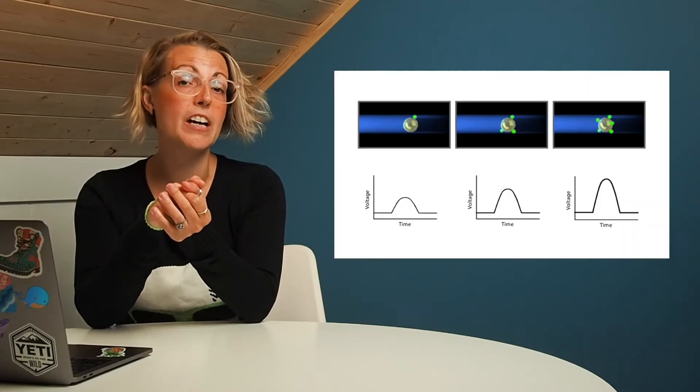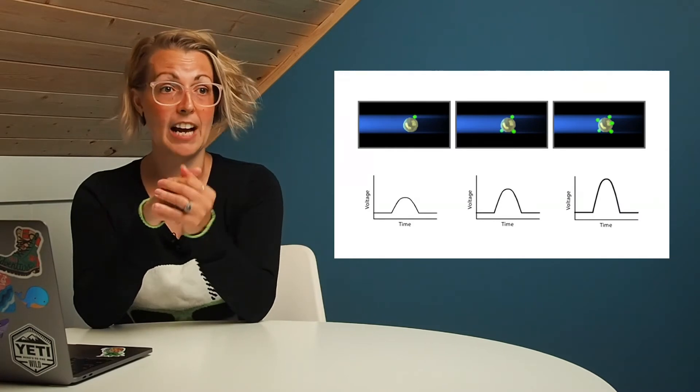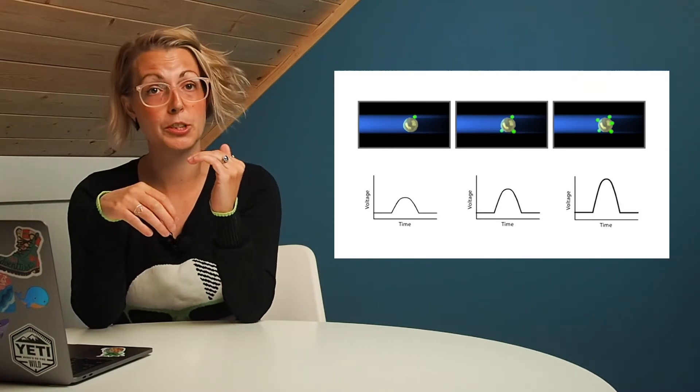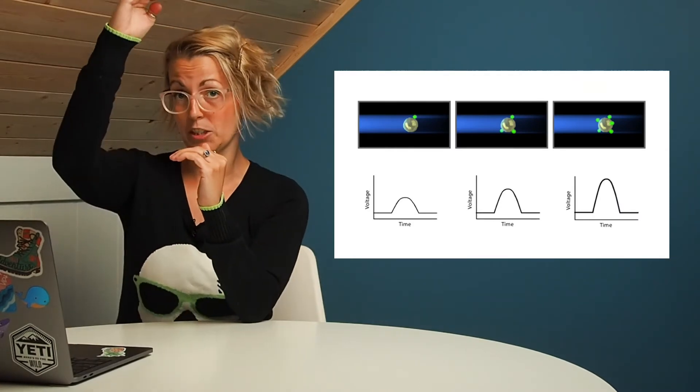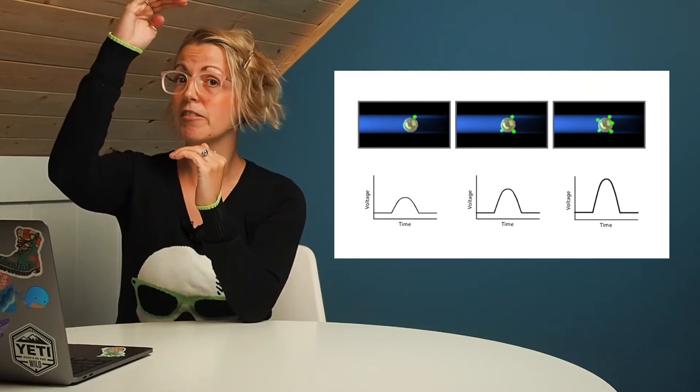When you look at your fluorescence data, you'll notice that some cells have a low level of fluorescence, and some cells might have a high level of fluorescence. This can be translated directly back to the voltage pulse. So a cell with a low level of fluorescence will have a lower voltage pulse than a cell with more fluorescence, which will have a higher voltage pulse. So this is how we can start to discriminate the difference between cells with a low level of fluorescence or a higher level of fluorescence.